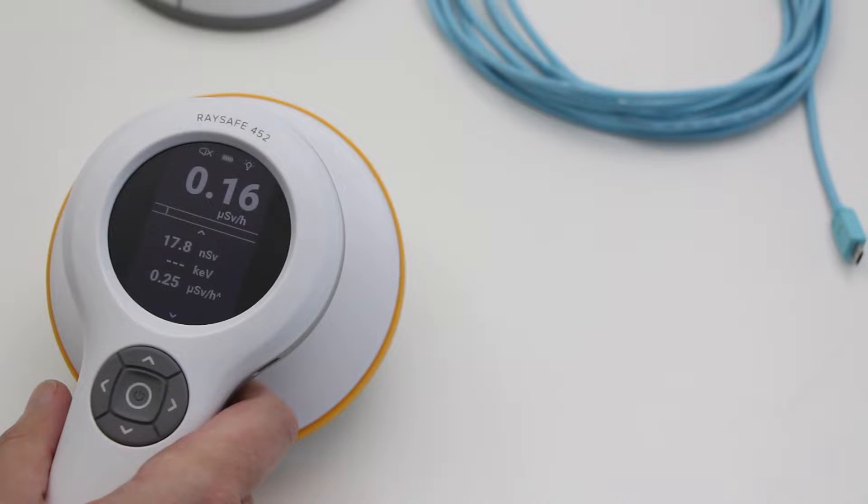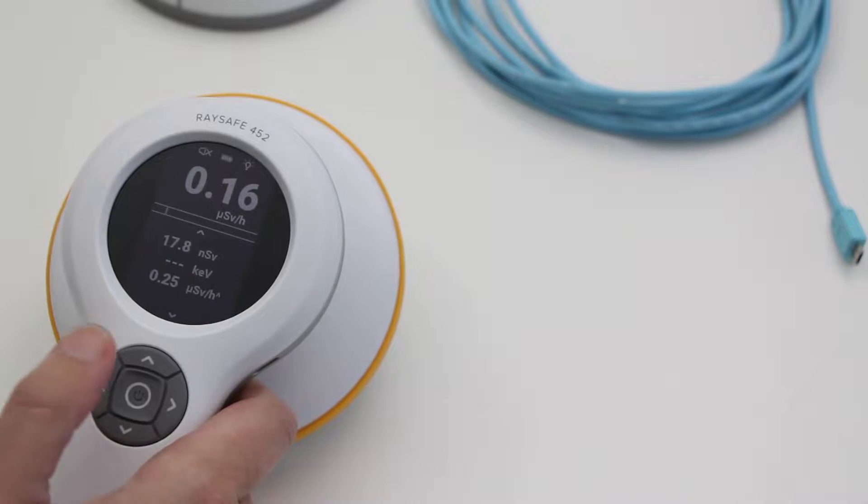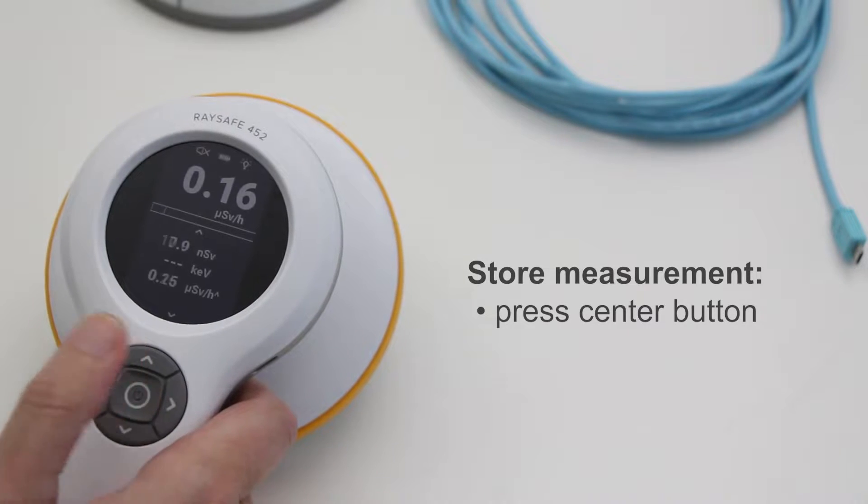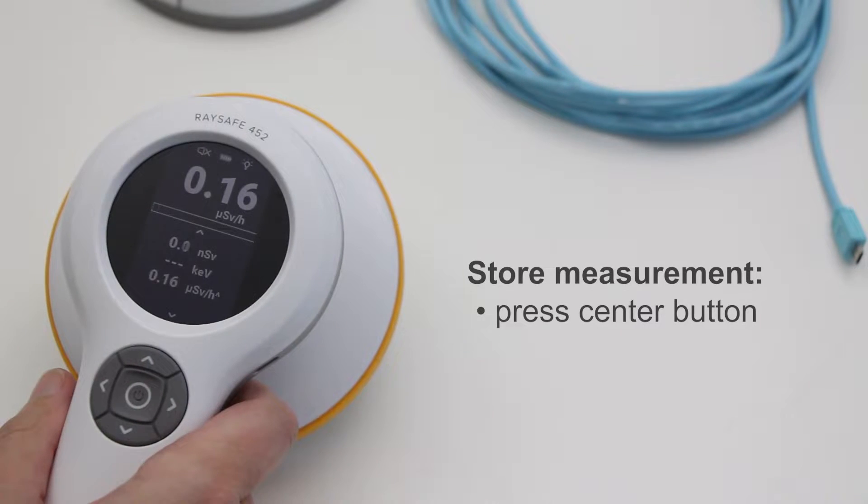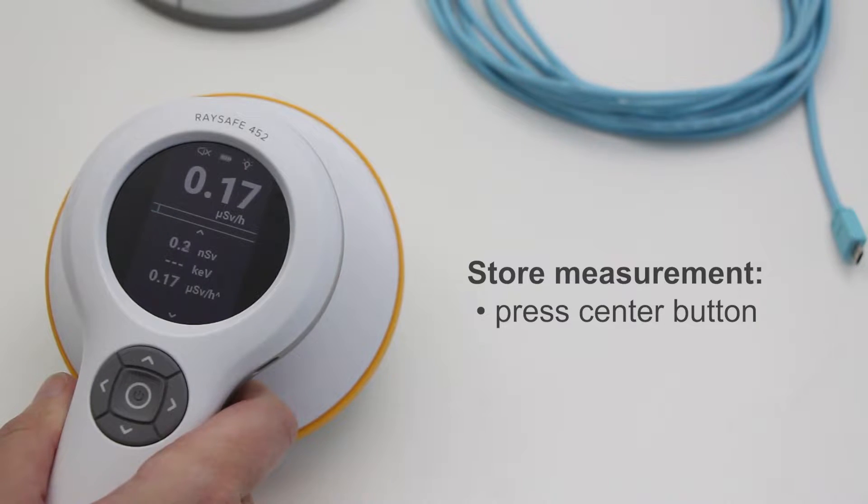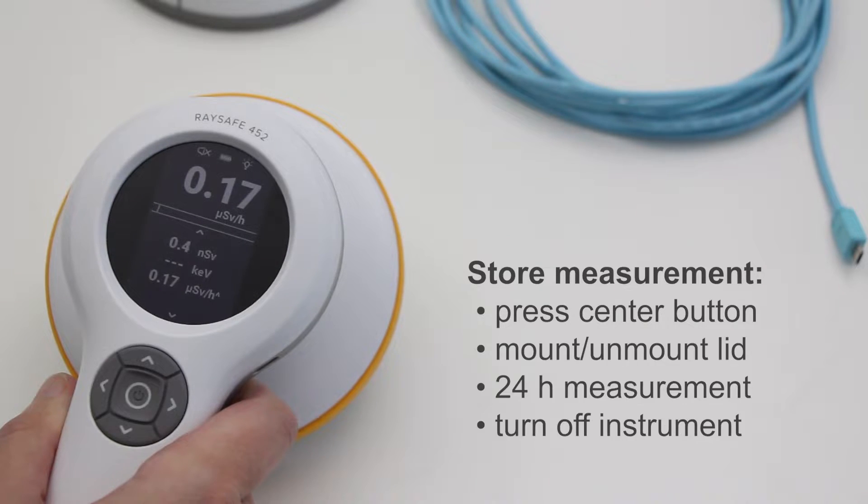If you want to define the start of a new measurement, press the center button. When you press the center button, the rate log and the readings on the screen are stored. Readings are reset and a new measurement begins.